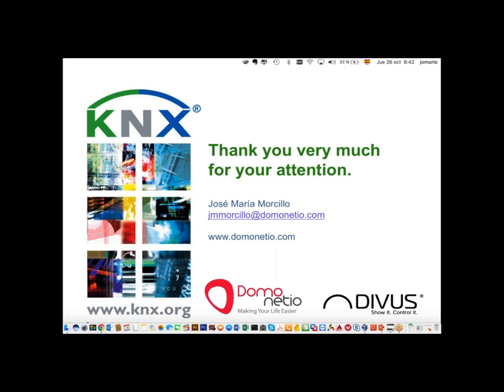Which device did you use to integrate the Sonos? Well, good question. In this case, I don't need to use any device. As I said before in the topology, Sonos is an IP device, and I have the KNX world and the IP world. The KNX server can talk both languages, IP and KNX. So the KNX server sends IP commands to the IP devices, in this case to Sonos. So I don't need any extra device to control the sounds. I can do it from the KNX server directly. Okay, perfect. Thank you for that answer.